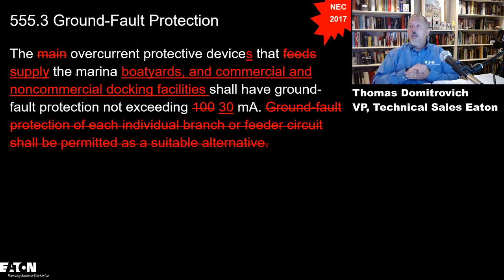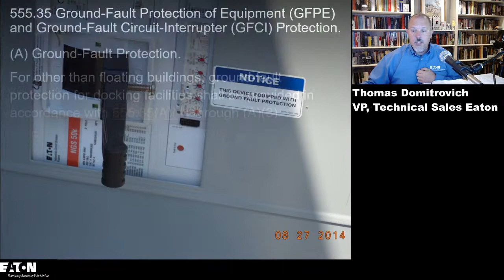Based upon that study, they went to 30 milliamps on all overcurrent devices, which proved problematic because 30 milliamps at the main was still a little bit too low of a number. So we went back to 100 milliamps in the 2020 cycle. So this is a picture, an example of what a device that's in a marina that actually has ground fault protection, and there's a label that shows you that. So here's the language that was settled on in the 2020 version, and they moved it from .3 to .35 because we completely rearranged Article 555 in the 2020 cycle.